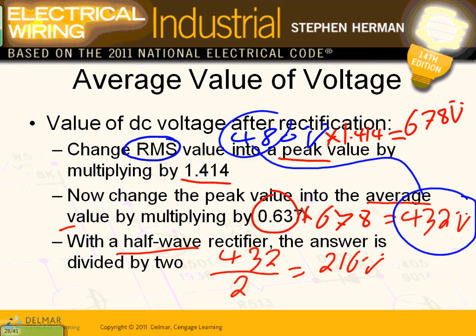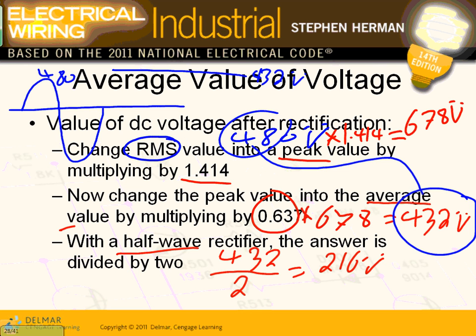Can you guys see what we're doing? Value-wise, here's my AC voltage, 480, and I convert it into almost pure DC. This is my 480, and this is 432 volt. So there are some losses in the voltage, right? The power delivered is still the same. You deliver the amount of power at different voltages.